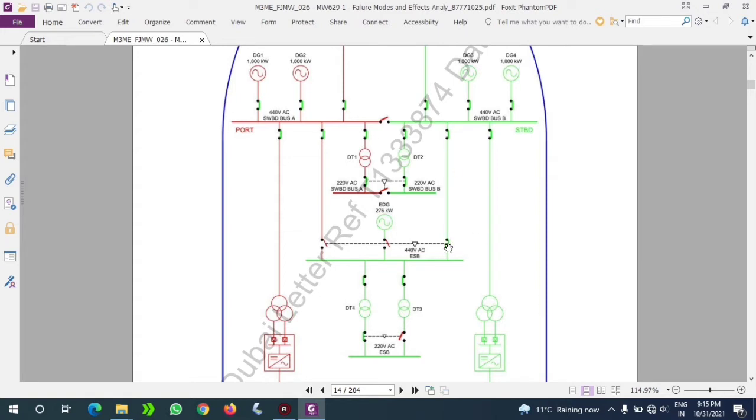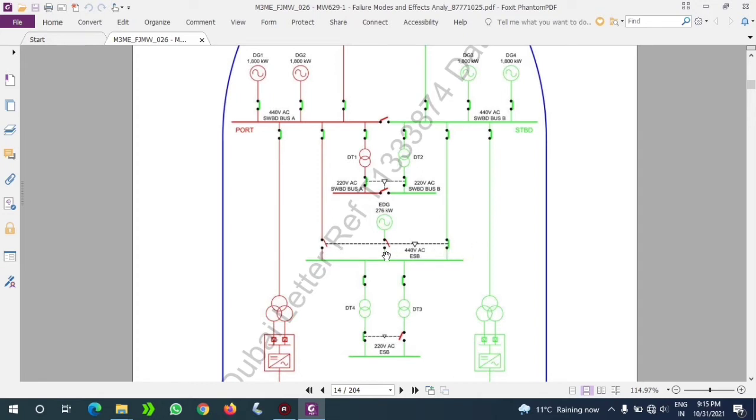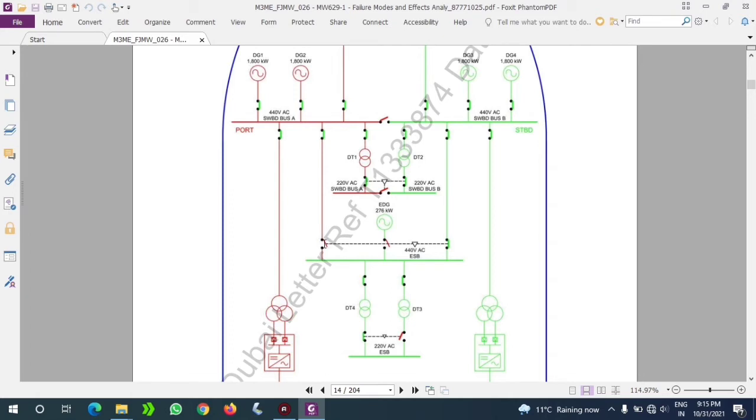The second thing is that you see the starboard bus bar is giving power to the emergency switchboard. Suppose our starboard bus bar failed, so that breaker - the green color breaker - will open and the red color breaker will close. These breakers are known as interlock breakers, which means these have connection to the two sides with one closed, one NC and one NO. You can see one generator in the middle of these two connections interlock - that is the EG, emergency generator.